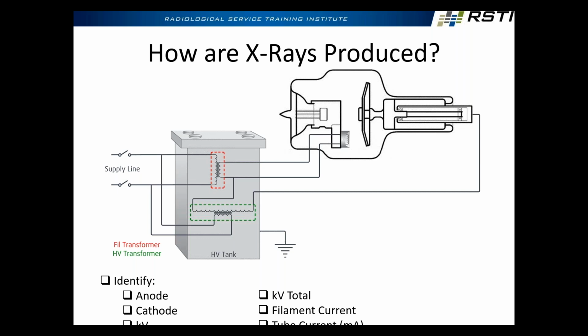The backside of that is usually an alloy of molybdenum and some other metals, sometimes rhenium. The shaft is also molybdenum because it's particularly crappy at transferring heat. We don't want heat to go this way because this is where our rotor is. The rotor has bearings in it. The bearings are actually part of the circuit. We conduct through these bearings, right? These bearings are inside the glass envelope. We've got a glass envelope that's connected to metal on both ends. It's a vacuum tube. Those bearings are getting lubricated once, when they build the tube. Some of these tubes might last 20 years. So it's probably a good idea to try to protect those bearings if we can't get in there and re-grease them, as it were.